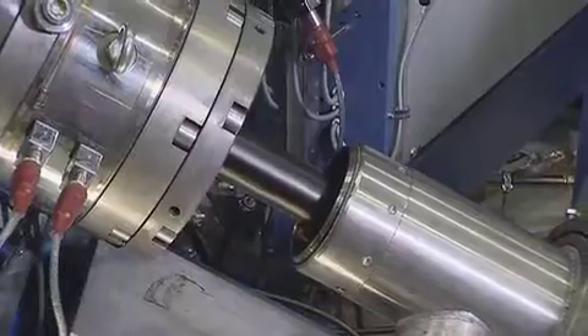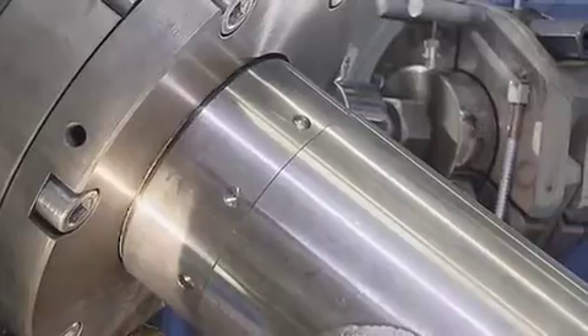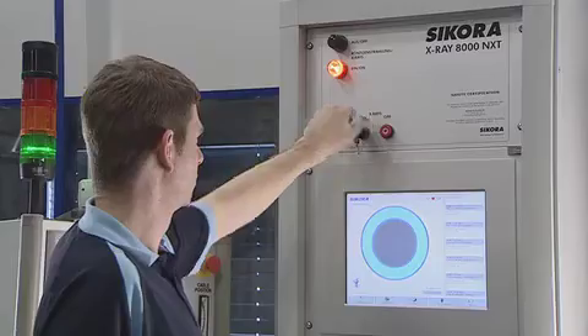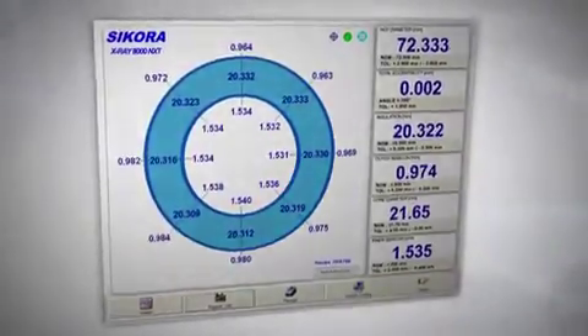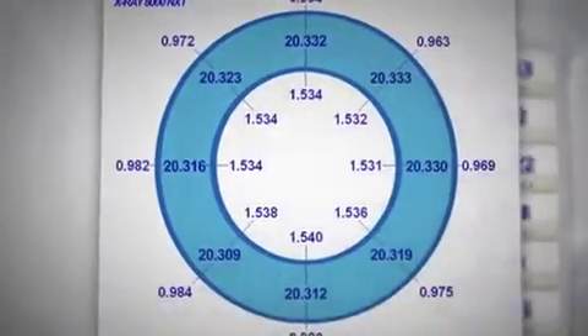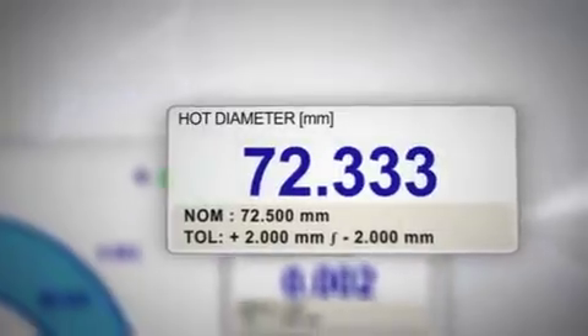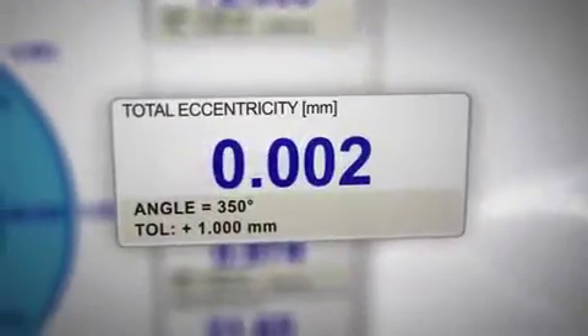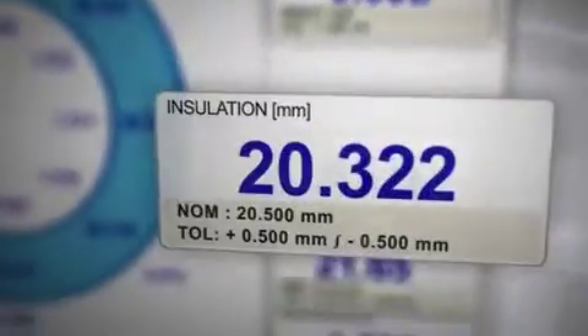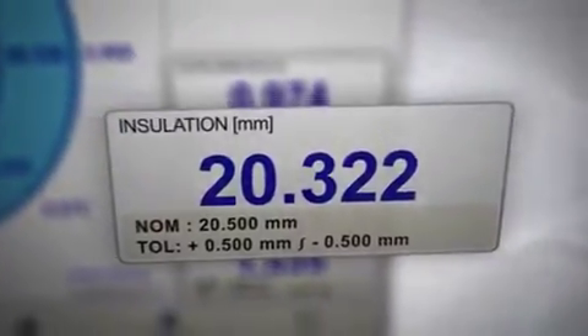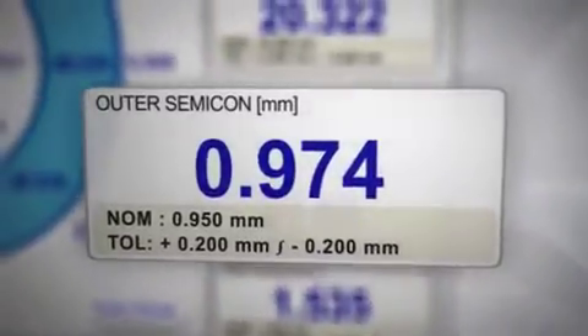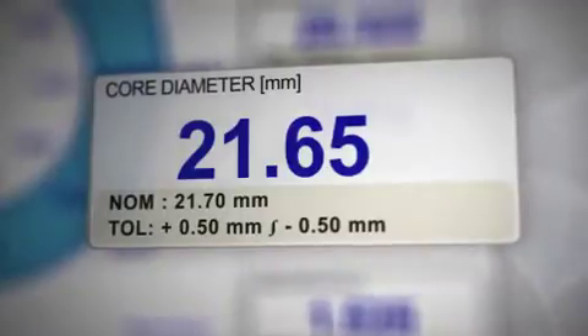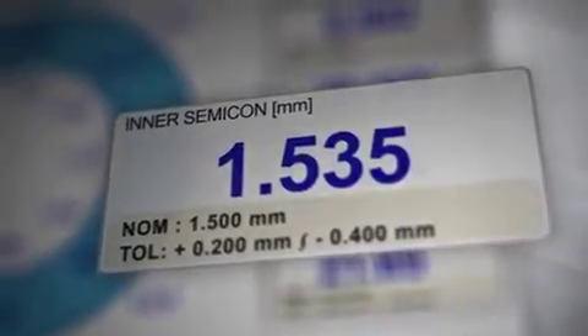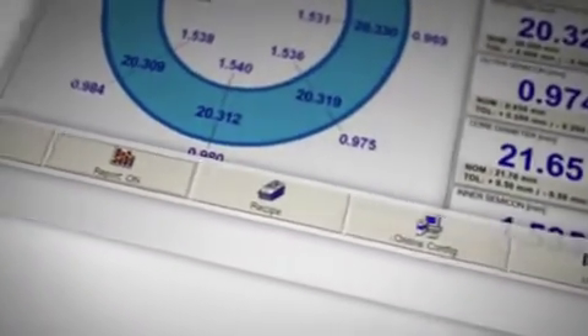The X-ray 8000 NXT provides accurate measuring values immediately after closing the telescopic tube and switching on the high voltage, without warm-up or calibration. Startup losses are minimized. The measuring values are graphically and numerically displayed at 8 points. The diameter, eccentricity, insulation, outer semiconductor, core diameter, inner semiconductor. All data are instantly readable at the display.